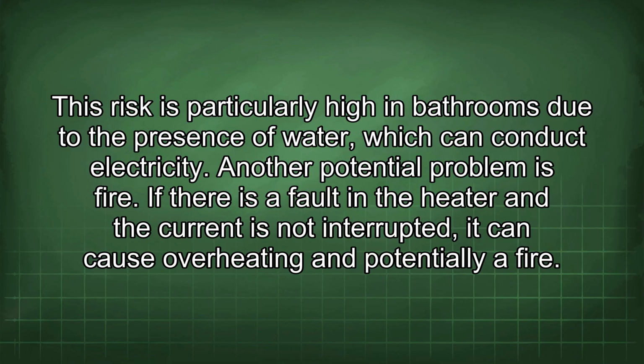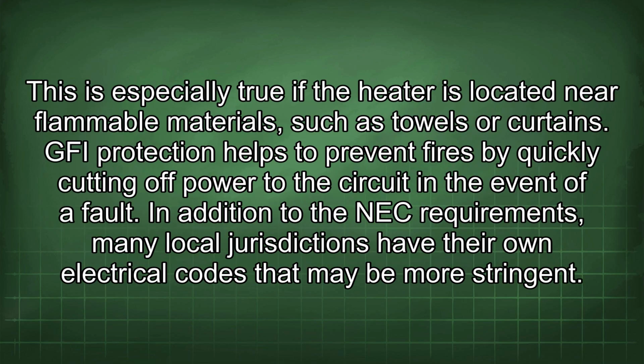Another potential problem is fire. If there is a fault in the heater and the current is not interrupted, it can cause overheating and potentially a fire. This is especially true if the heater is located near flammable materials, such as towels or curtains. GFI protection helps to prevent fires by quickly cutting off power to the circuit in the event of a fault.